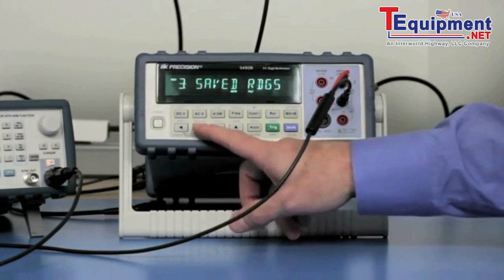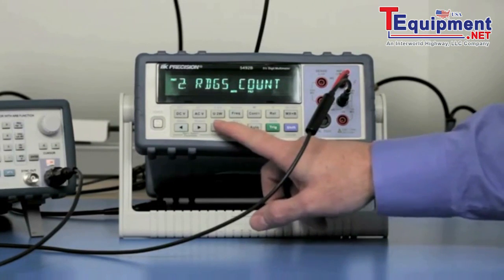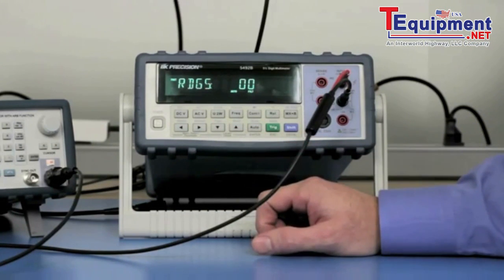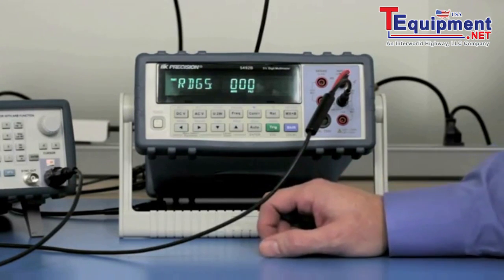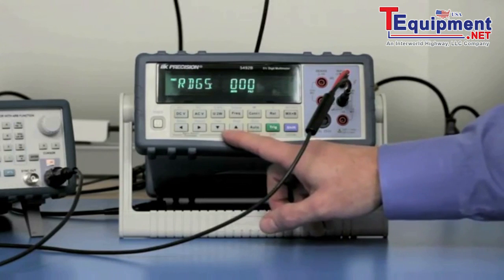Next, we need to set the readings count. This is how many readings you want to record. And the 5492B can record up to 512 readings. So I'm going to set it for 512.